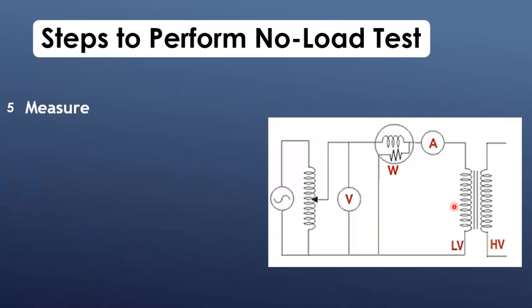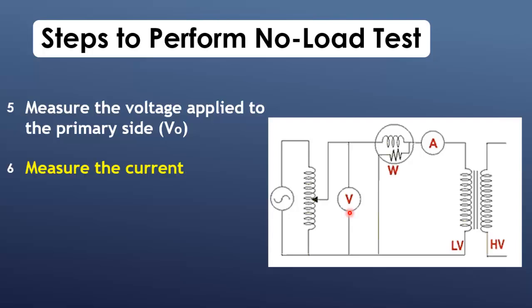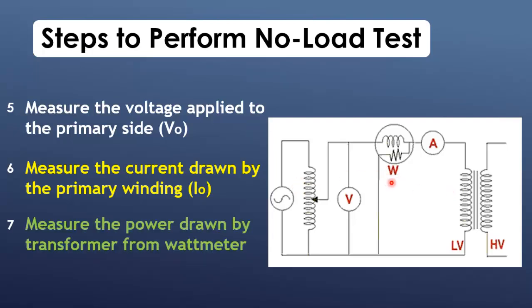Now after energizing the transformer at rated voltage, measure the voltage applied to the primary side V0. Note down the current drawn by the primary winding I0. Note down the power drawn by transformer using wattmeter.